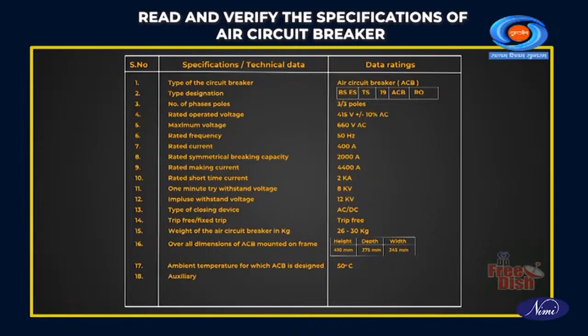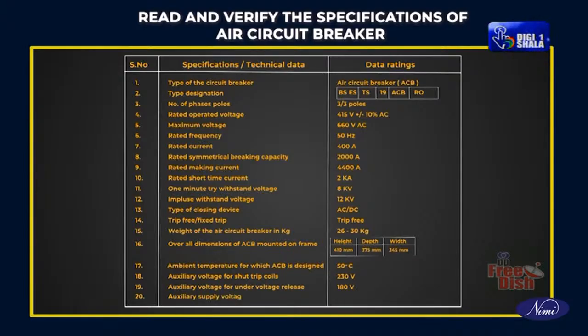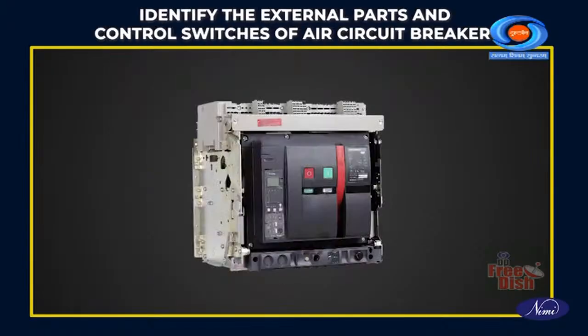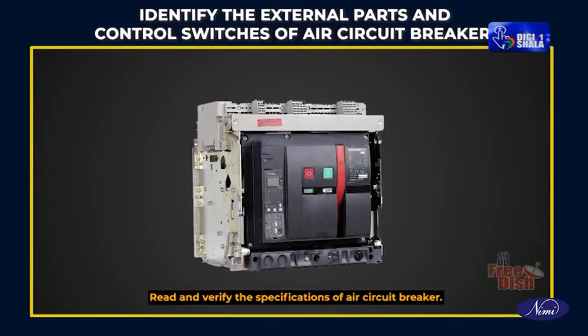Auxiliary voltage for shunt trip coils: 230 volts. Auxiliary voltage for under voltage release: 180 volts. Auxiliary supply voltage for motor drive: 415 volts, 3 phase. Identify the external parts and control switches of the air circuit breaker. Read and verify the specifications of the air circuit breaker.